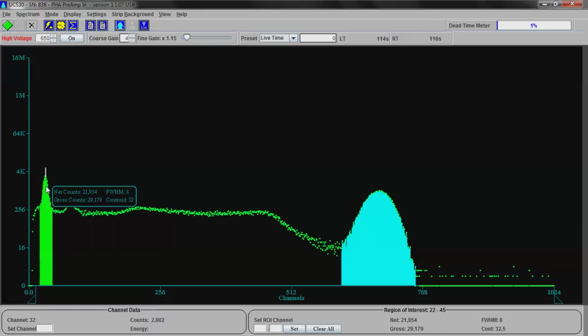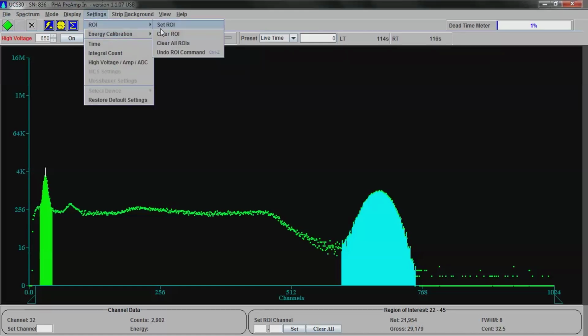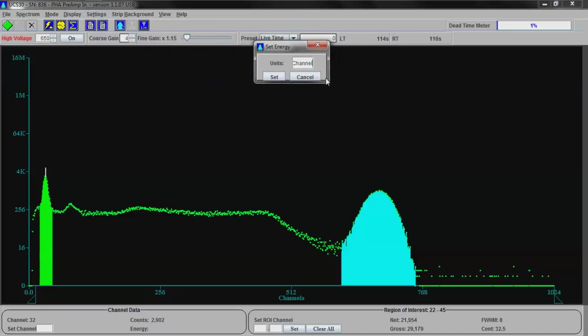Channel 32 is equal to 32 kiloelectron volts, and we're going to pick that channel 681 is equal to 662. This is just like, you remember in school you had y2 minus y1 over x2 minus x1, and you had the slope of an equation. It's kind of the same sort of thing. It isn't really as complicated as it sounds. We'll do a 2-point calibration. The machine wants to know what kind of units we're using: feet, pounds, inches. In this case, we're going to use thousands of electron volts.